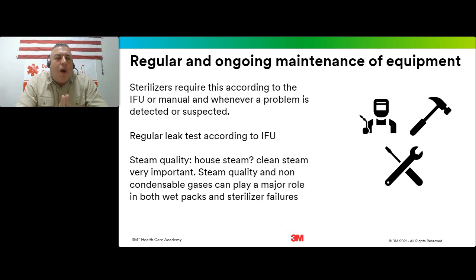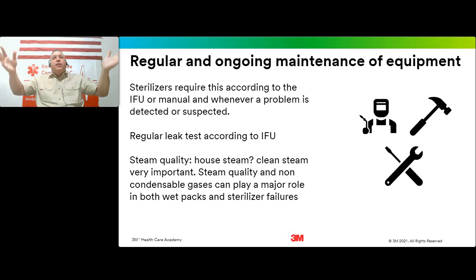But the steam quality is super important. We could have non-condensable gases and other things that can contribute to wet packs and also contribute to sterilizer failures. That steam quality, you open up your autoclave chamber and you look at the walls of your chamber, that's going to be reflective of what your instruments will eventually look like.